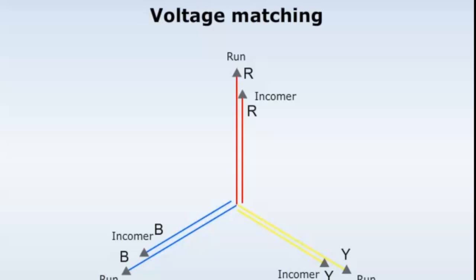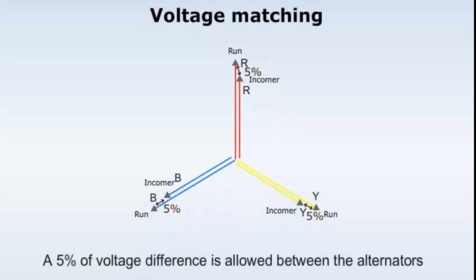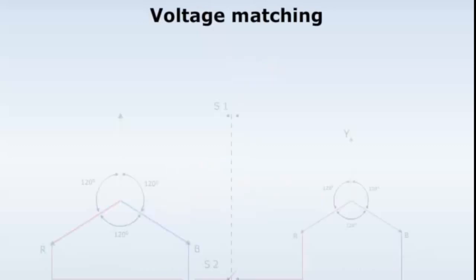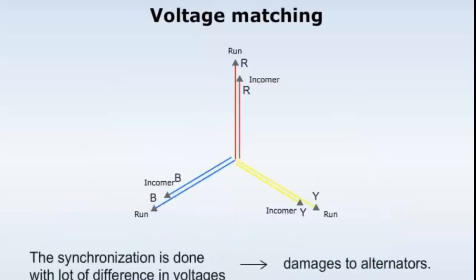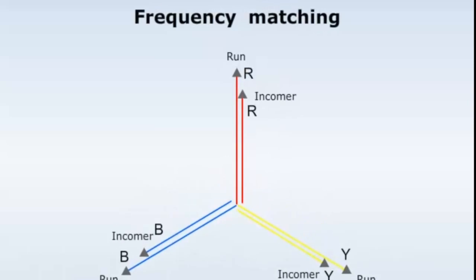The second condition is that the voltage of the incoming alternator should match the voltage of the running alternator. For proper synchronization, a 5% voltage difference is allowed between the alternators. If there is a difference in voltage levels of more than 5%, there will be a flow of large amounts of circulating currents in the internal circuit connecting the two alternators. If synchronization is done with a large voltage difference, it may cause damage to both alternators.